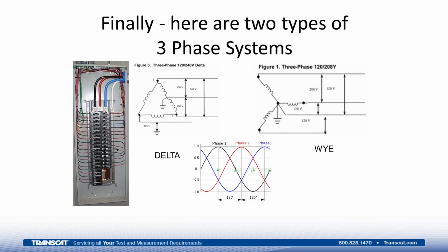I then would have the ability to put CTs either around the three conductors. The black, the red, and the blue could each have a CT put around them, which would measure the current going into this entire panel, where I would not be able to segregate what is being fed to any load.